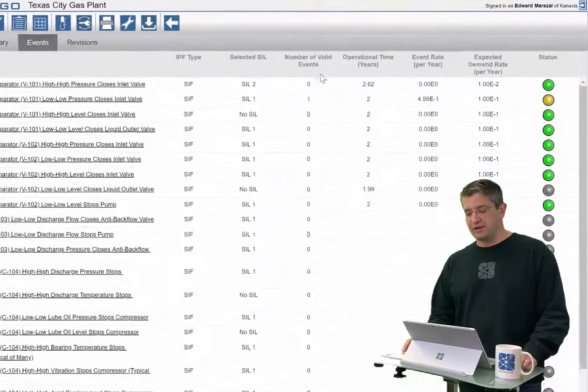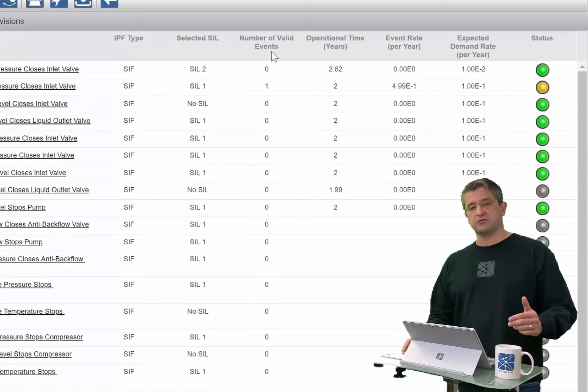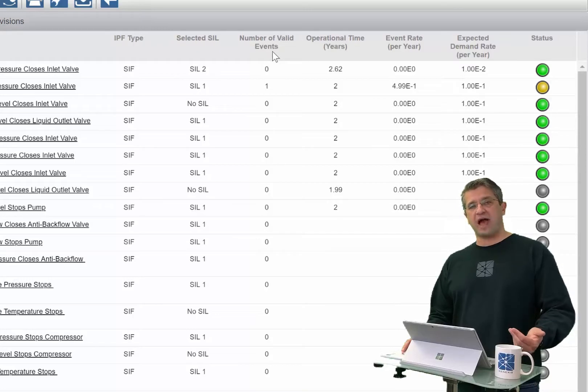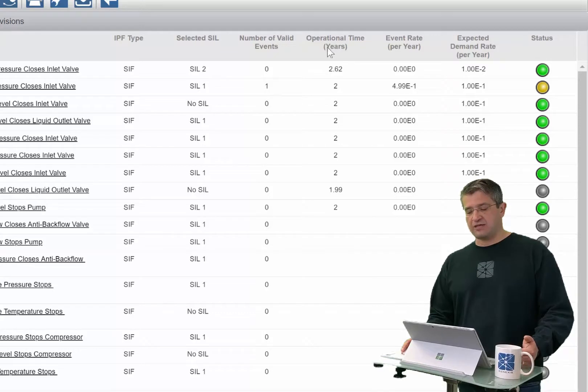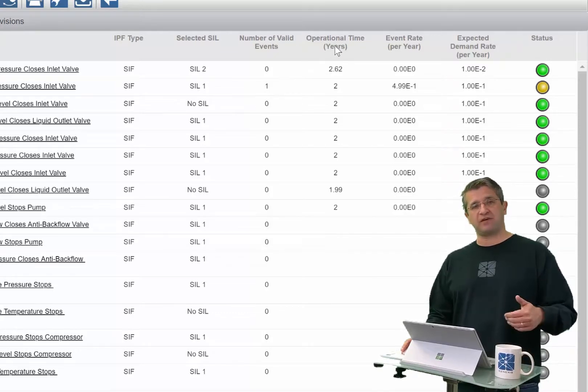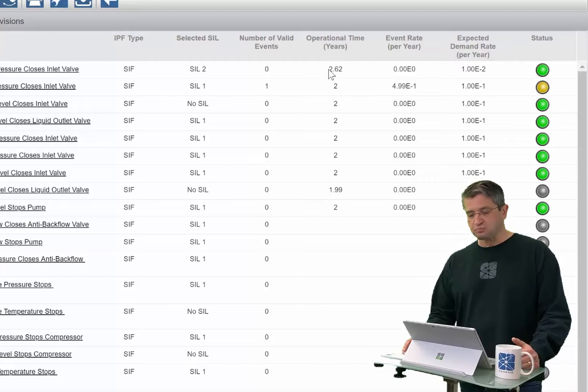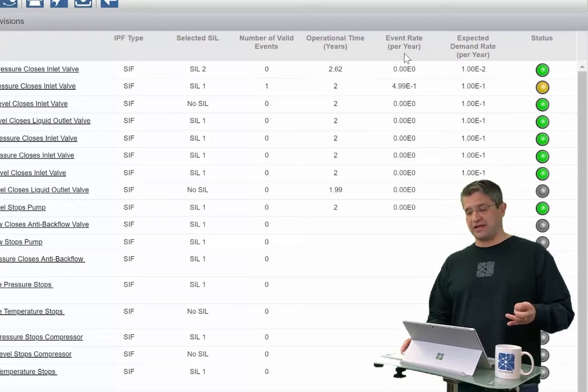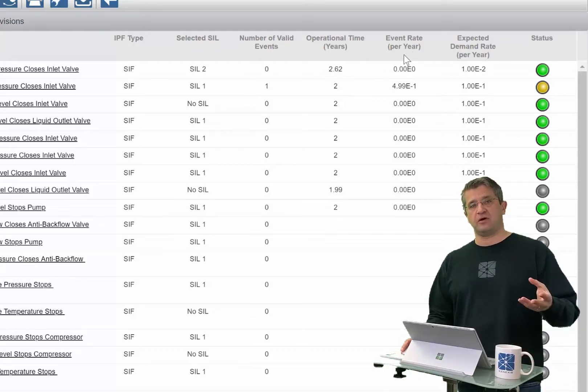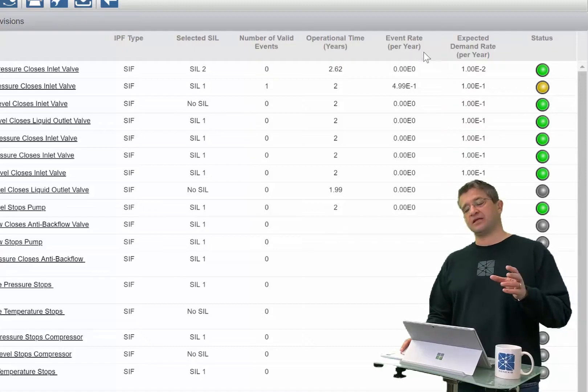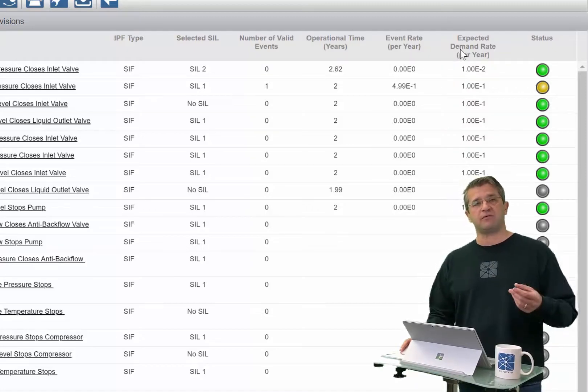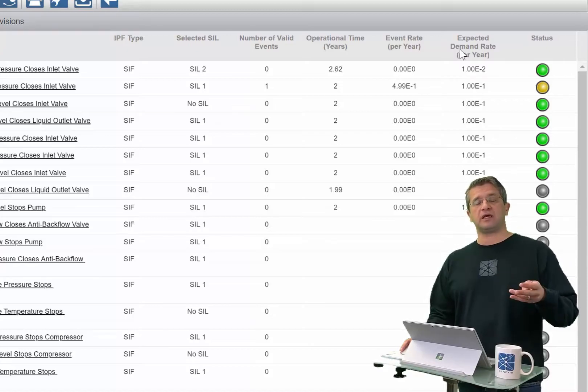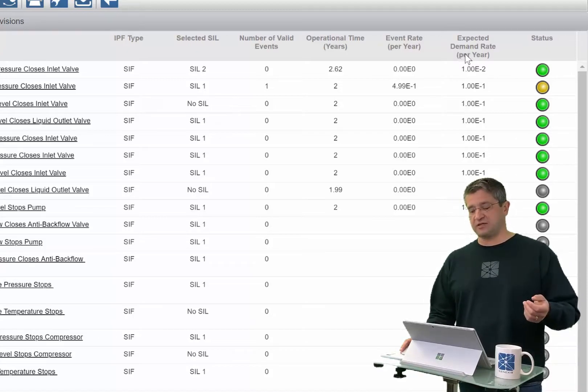Beyond that, the next row includes the number of valid activation events that have occurred with that particular IPF, the operational time that IPF has been in service, which allows us to calculate an event rate. That event rate can then be compared against the expected or assumed event rate shown in the risk analysis studies.